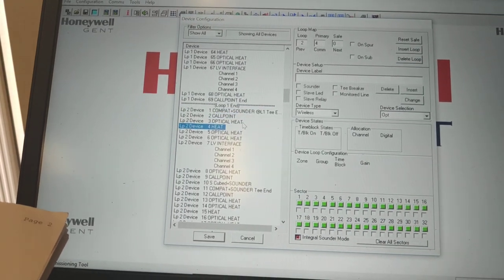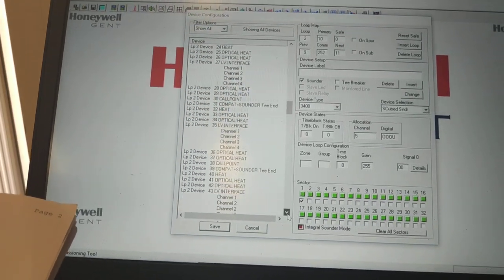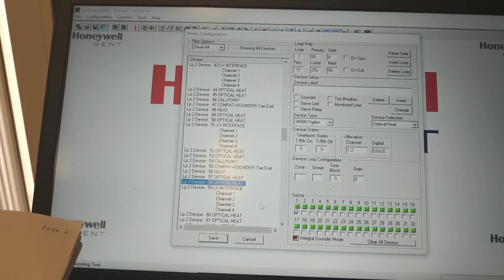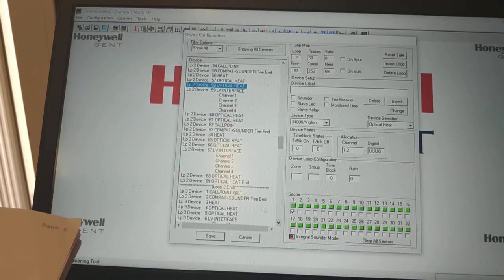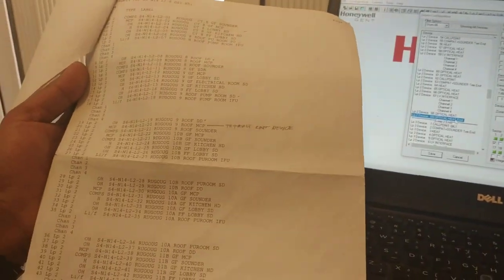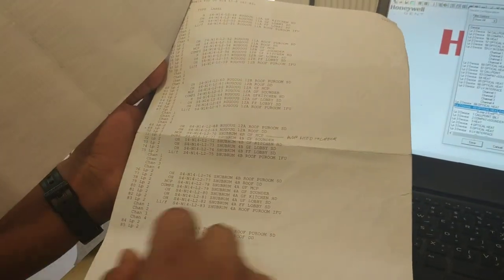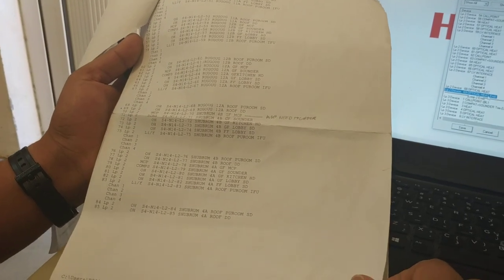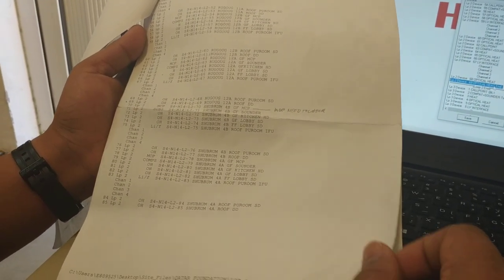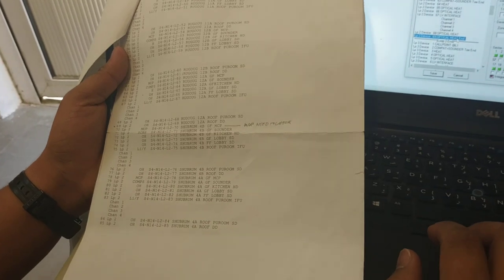I need to check Loop 2 — how many devices in Loop 2? Loop 2 also has no labels. 69 devices also in Loop 2. I will check here as per the existing label list. Loop 2 — how many devices now? 85. There are some bypasses here, so we need to check this one by one, line by line. Different areas also here.